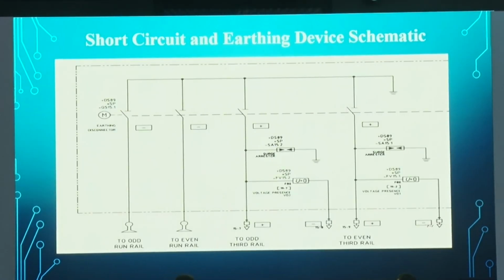There are two types of short circuiting devices available. One is 4-pole, in which you can connect both upline and downline along with third rail. And there is another way of having 2-pole short circuiting device, in which one side of the rail, that means upline or downline, can be connected to the third rail. We are using both of them. In depots we are using 2-pole, and in main line we are using 4-pole isolators.